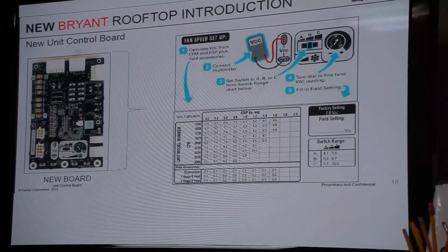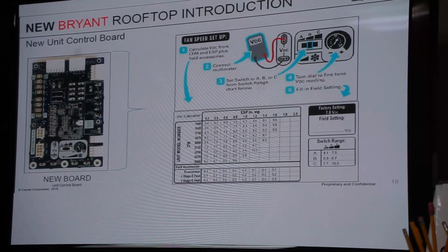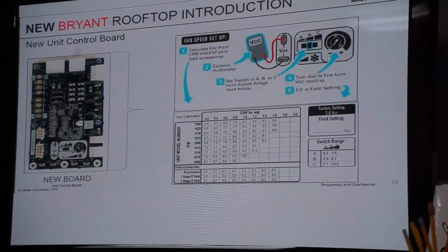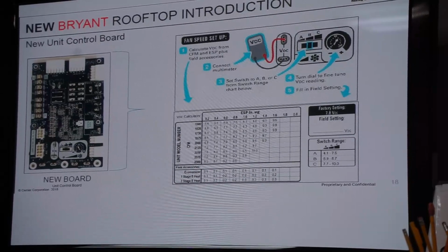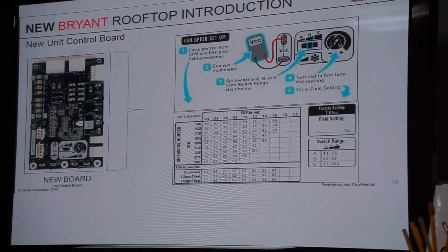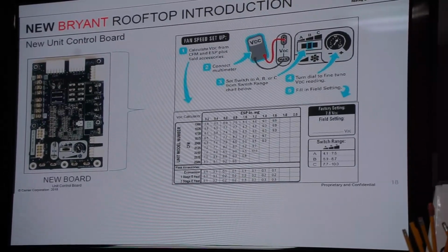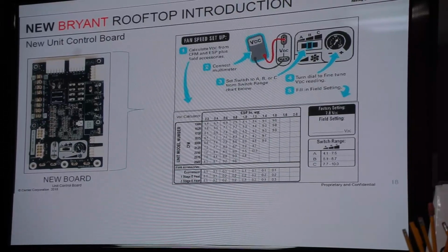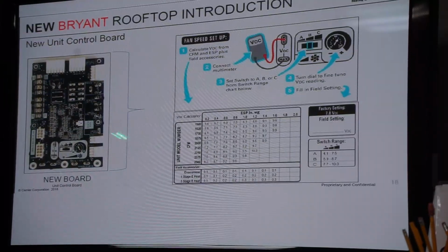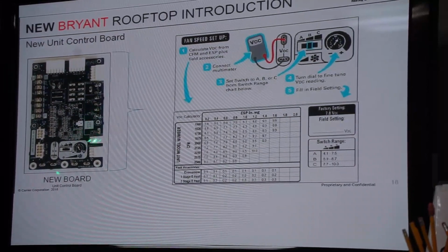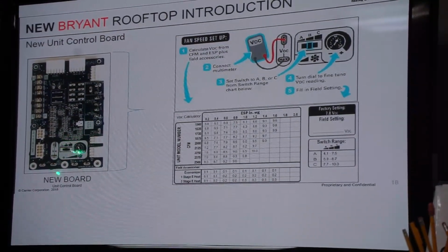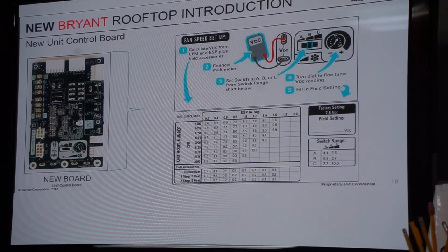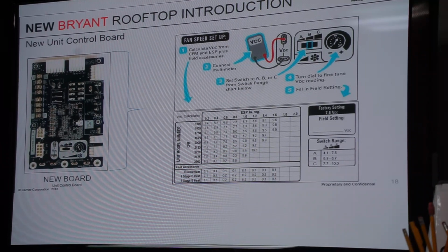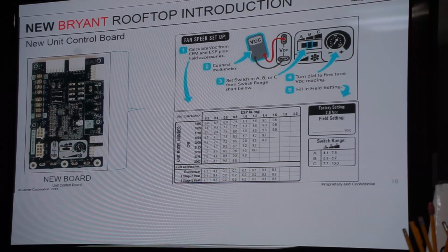But what this does, that ECM on the fan generates 10 volts. So it's got three-phase or single-phase power going to it at all times. The module in the motor generates 10 volts. It comes back to our controller on these two terminals. We manipulate that 10 volts and send it back to the motor with our speed selection. And that's key to have in your head, as to where that voltage is coming from, for troubleshooting.